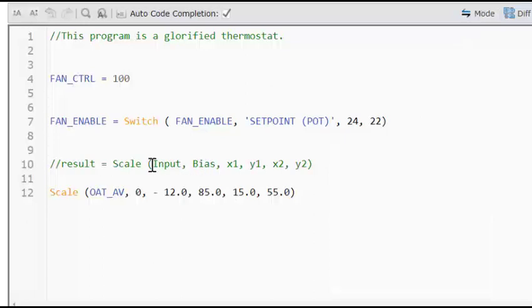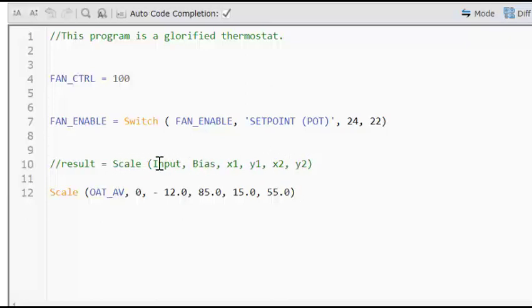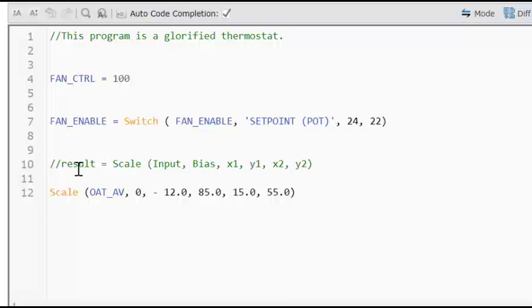Now, looking at our example here that we copy and pasted from the help file, you can see we got our scale function all lined up with all of its different parameters. But it's going to return a value. It's going to make that calculation based on what it sees with outdoor air temperature and then give us our heating hot water temperature set point. But it wants to store that information somewhere. Well, how the syntax works is it's got to go into something. It has to go into a box of some sort. And that's where our variables come in.